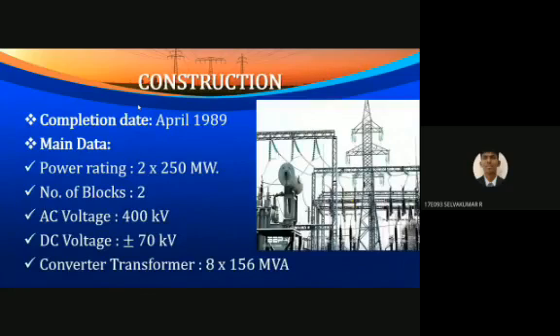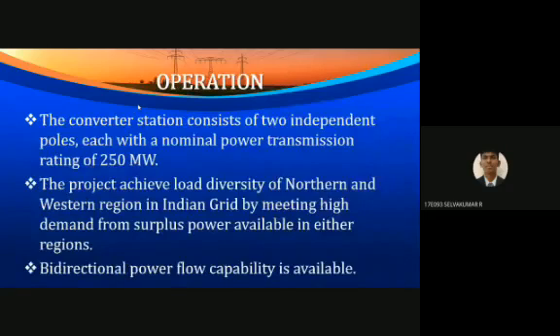Construction-wise, the station has two blocks, each carrying a power of 250 megawatts. The AC voltage rating is 400 kilovolt and the DC voltage rating is plus or minus 70 kilovolt. The station has eight converter transformers, each with a rating of 156 megavolt-ampere. This project was completed in April 1989.